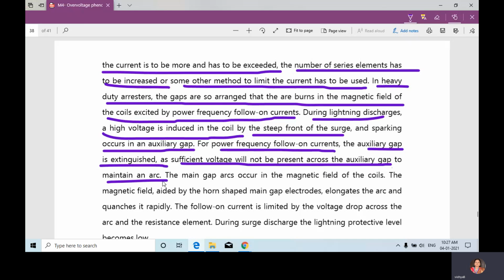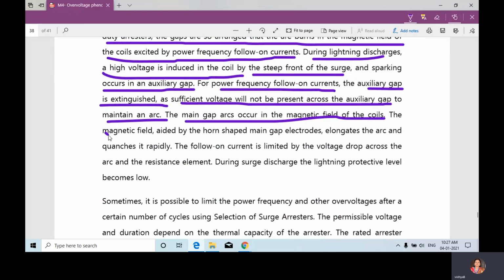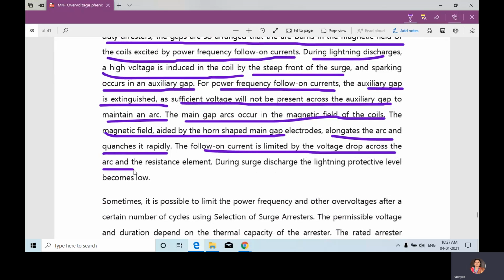Sufficient voltage will not be present across the auxiliary gap for what? To maintain an arc. The main gap arc occurs in the magnetic field of the coil. The magnetic field, aided by the horn shaped main gap electrodes, elongates the arc and quenches it rapidly. The follow-on current is limited by the voltage drop across the arc and the resistance element. During surge discharge, the lightning protective level becomes low.